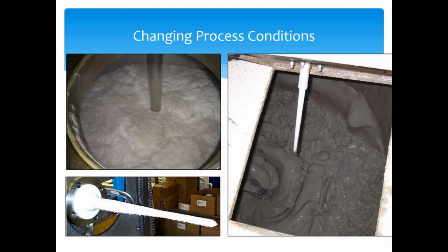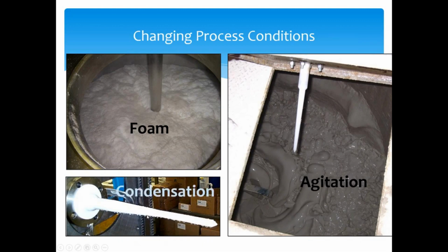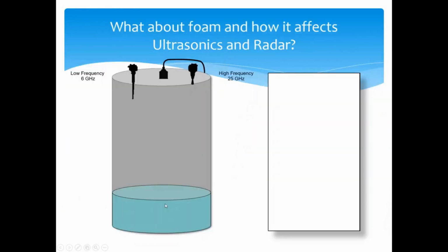Here are some different changing process conditions that we've talked about, or we're going to talk about. We'll have foam, which we'll spend a lot of time on, agitation inside of a tank or a vessel, and then condensation or buildup on a product. One of the most common things that I see in Florida is foam, all over the place in lift station applications. I see it plenty of times in process plants where we're doing any sort of reaction. So we're going to talk about the 3 different types of foam, and about different frequencies of radar and ultrasonic and how each would fare in a foamy application.